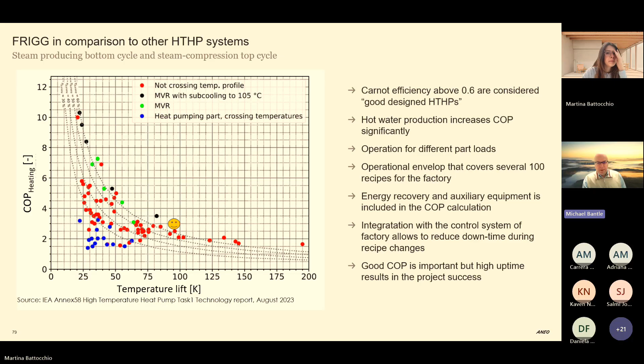How much dead time do you basically get? With the current concept and integration, we have put a lot of effort into it to start the heat pump on Monday morning and have it continuously running while the factory does all the recipe changes until Friday. This gives us not only a COP, but also the gigawatt hours supplied over time. One of the main challenges in the project was to minimize this dead time, where the heat pump needs to stop. And now we have basically zero stops in the heat pump.